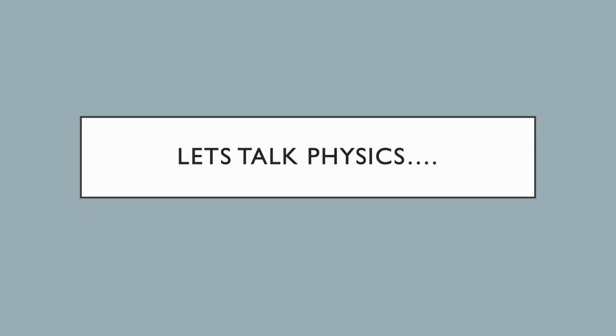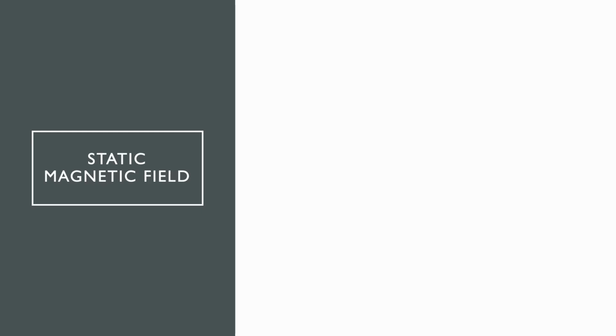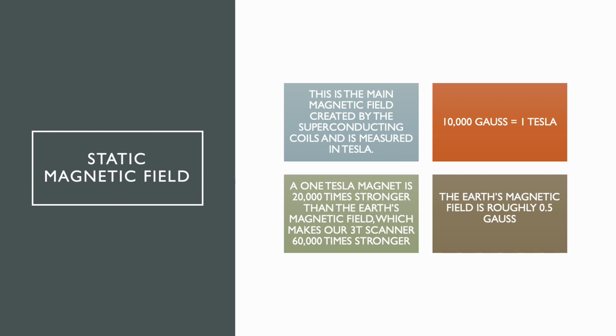Let's have a deeper look and dive into a little bit more physics. First, the static magnetic field. Static magnetic fields are magnetic fields that do not vary with time. The static magnetic field is the main magnetic field created by the superconducting coils and is measured in Tesla. 10,000 gauss equals 1 Tesla. The Earth's magnetic field is roughly 0.5 gauss. Therefore, a 1 Tesla magnet is about 20,000 times stronger than the Earth's magnetic field, which makes our 3 Tesla scanner about 60,000 times stronger.